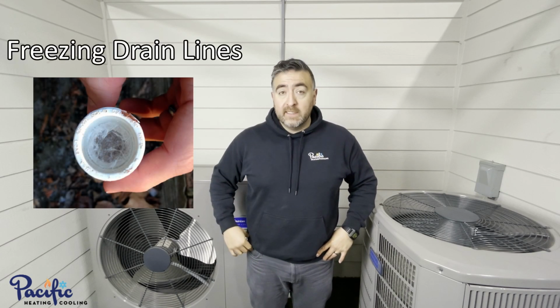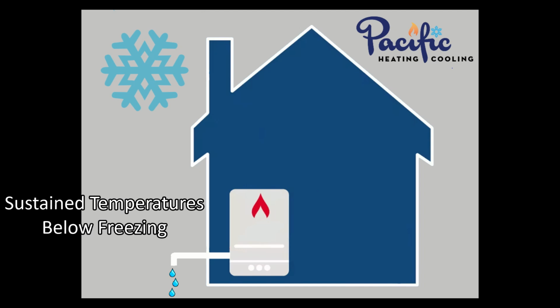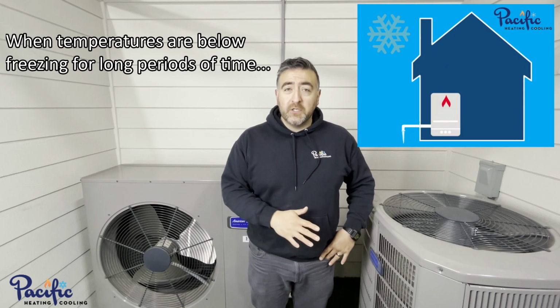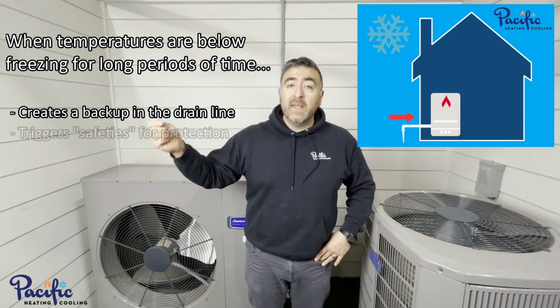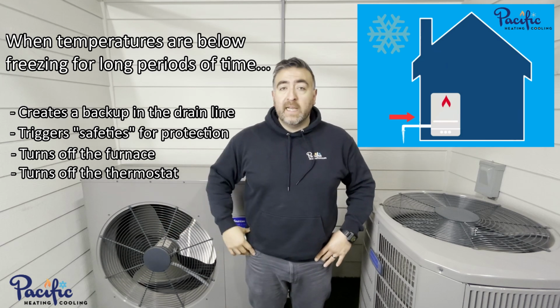A common issue for most condensing gas furnaces, or high-efficiency gas furnaces, is freezing drain lines. Here's what can happen when outdoor temperatures get below freezing. That condensate drain line that pushes water from the unit outside of the home can potentially freeze. When condensate drain lines freeze with low outdoor temperatures, that backup of moisture can make its way to the furnace through the drain line, tripping the safeties, and the system will protect itself by shutting off the furnace or the thermostat.